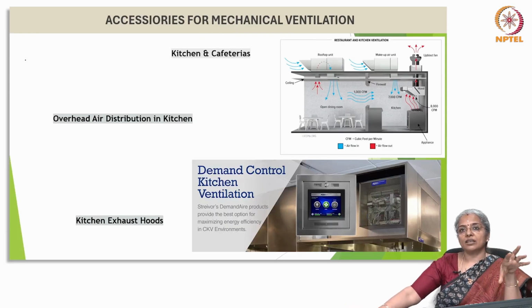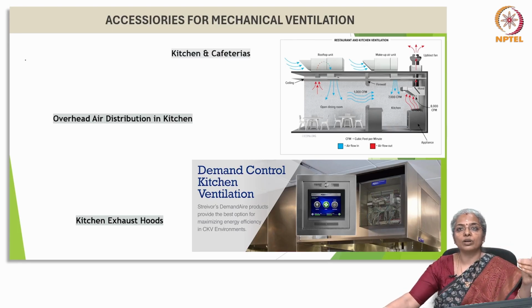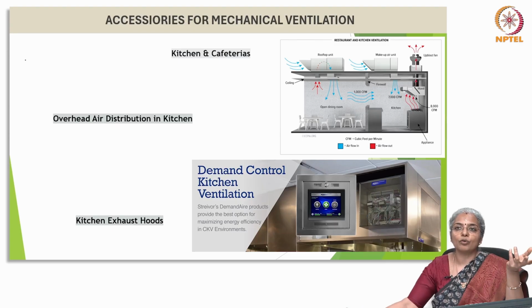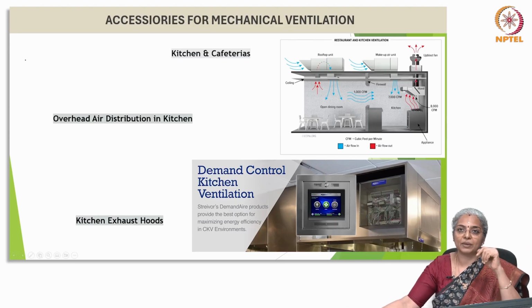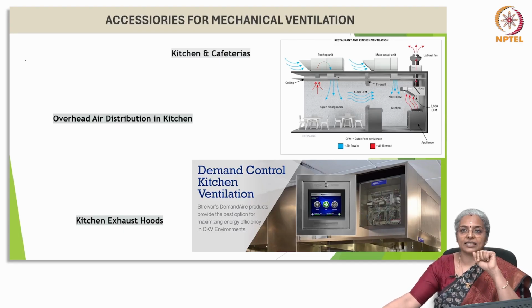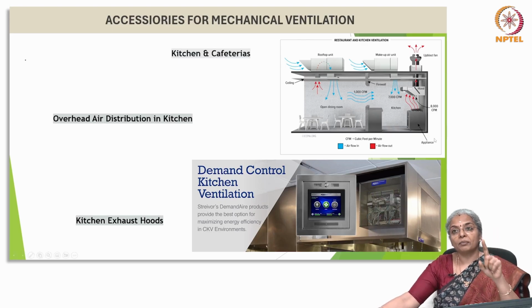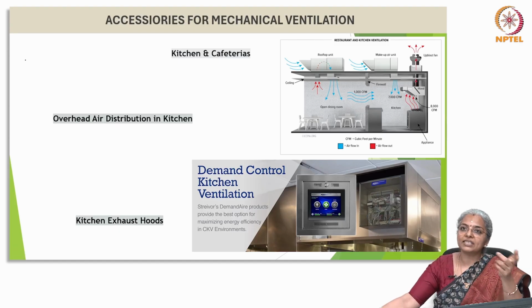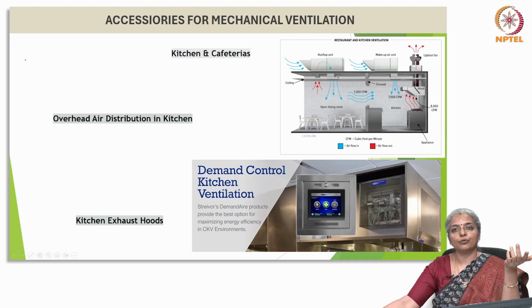Now, in food service HVAC systems, additional air exchanges or separate mechanical systems could be desired or required to minimize the unwanted spread of odors from the space to other parts of the building. Exhaust hoods are required over the cook lines to capture cooking odors and prevent the smoke from entering the general flow of air into other spaces. Commercial kitchen ventilation is a very important energy consumer in the cafeteria space. We need to make an effort to optimize exhaust performance because it can lead to measurable energy and financial savings. Relevant HVAC standards for commercial kitchens are already prescribed in various standards like ASHRAE and ISHRAE, which we should follow.